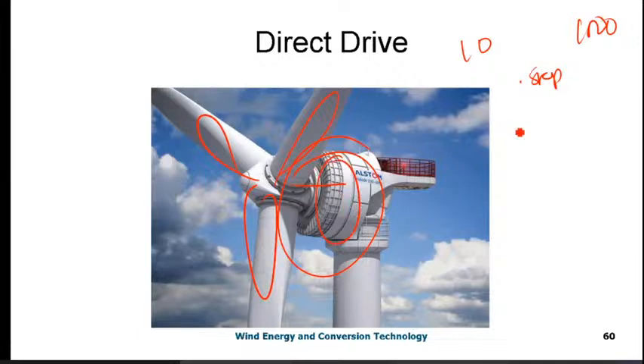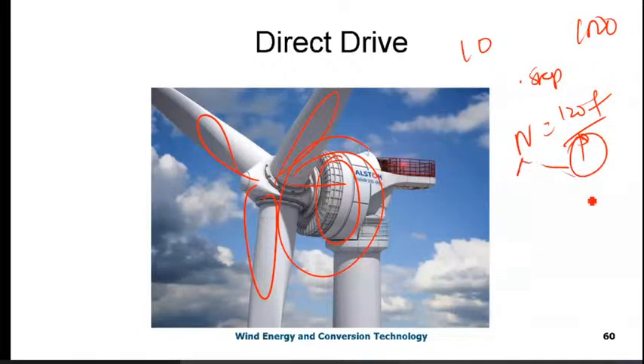How is it possible? Speed equals 120F by P, where P is the number of poles. If you increase the number of poles, the speed decreases, since it is inversely proportional. If the number of poles is, say, 100, then the speed can be adjusted accordingly. So this is the way it has been designed.